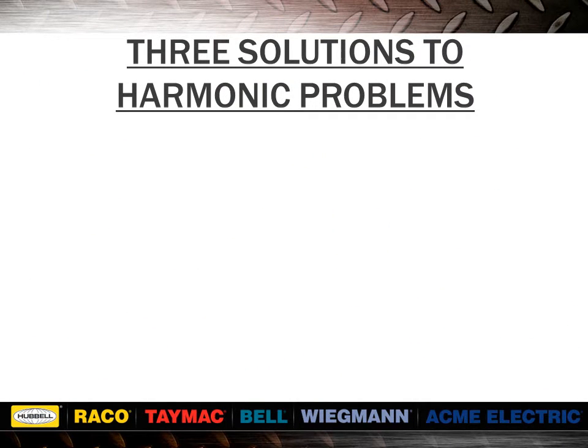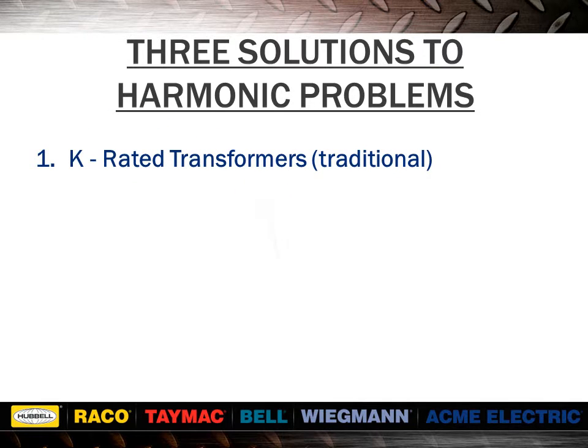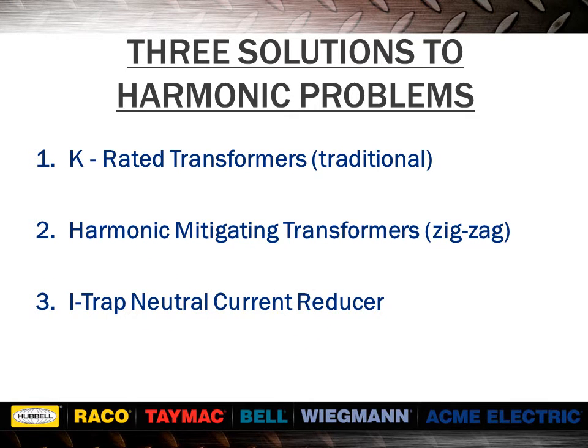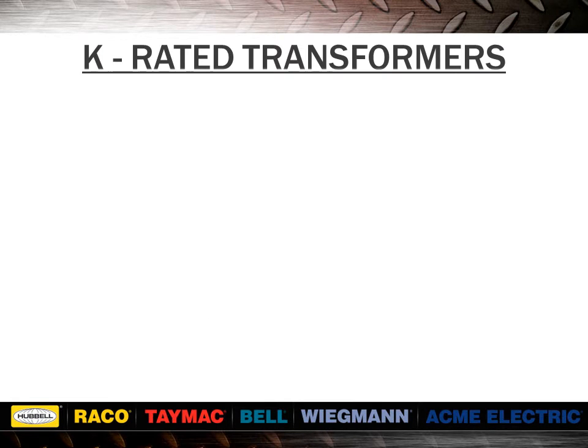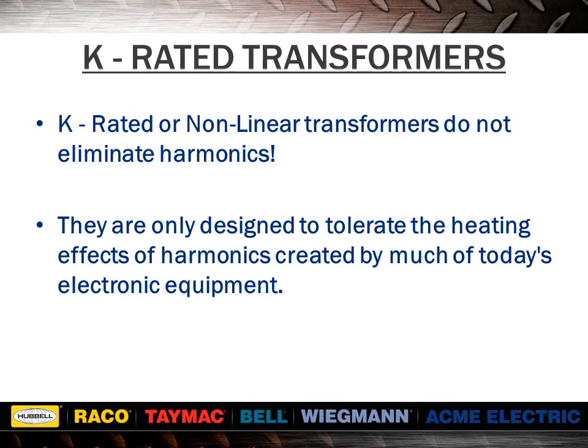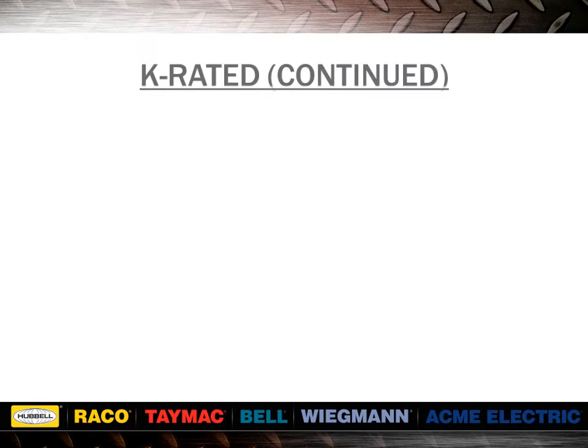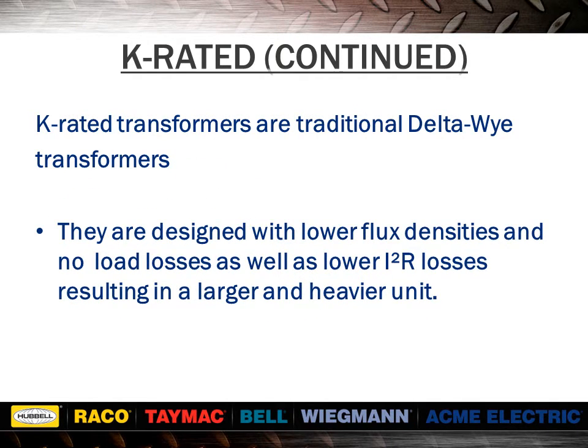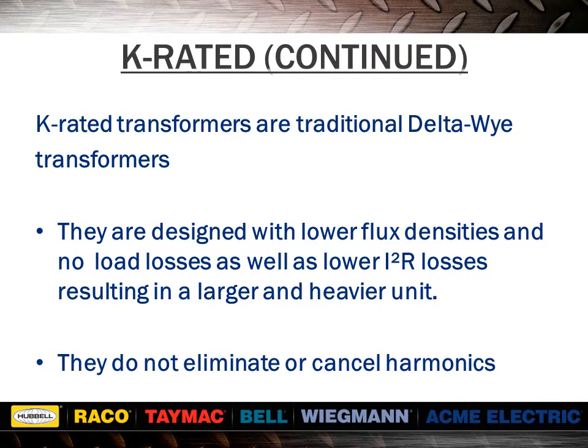There are three solutions to harmonic problems: k-rated transformers, harmonic mitigating transformers, and I-TRAP neutral current reducer. K-rated or non-linear transformers do not eliminate harmonics; they are only designed to tolerate the heating effects of harmonics created by much of today's electronic equipment. K-rated transformers are traditional delta-Y transformers designed with lower flux densities and no-load losses, as well as lower I²R losses, resulting in a larger and heavier unit. They do not eliminate or cancel harmonics.